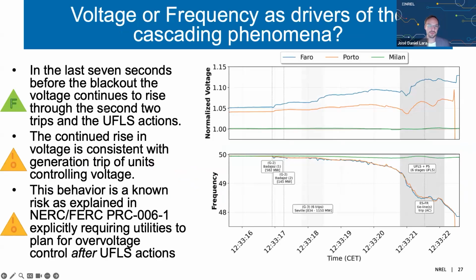So again, in the last few seconds before the blackout, you can actually see this rise of voltage. I'm zooming in here. And this behavior actually makes things worse because as the under-frequency load shedding starts to act, you're just making the voltage problem worse. Now, this behavior in the US is a known risk, although it's not explicitly regulated. The only mention of this kind of problem, just to emphasize how uncommon it is, is in NERC PRC-006, which just says, when you're tuning your under-frequency load shedding, be careful of overvoltages. But it's not properly regulated, right? It's just a known risk.